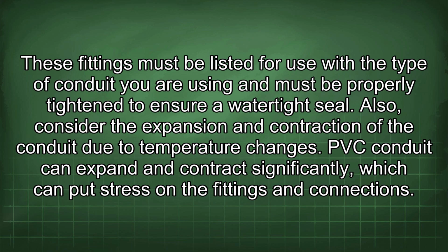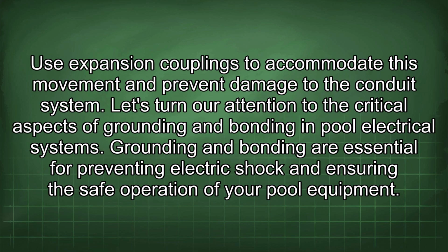Also, consider the expansion and contraction of the conduit due to temperature changes. PVC conduit can expand and contract significantly, which can put stress on the fittings and connections. Use expansion couplings to accommodate this movement and prevent damage to the conduit system. Let's turn our attention to the critical aspects of grounding and bonding in pool electrical systems.